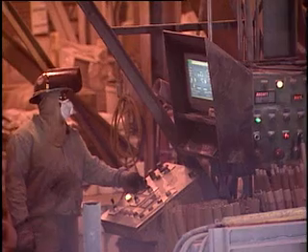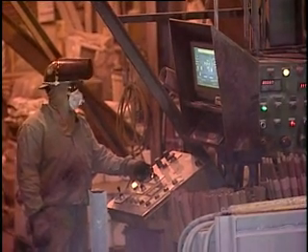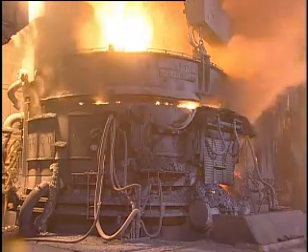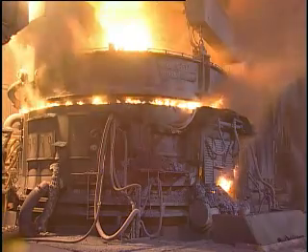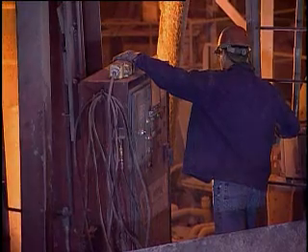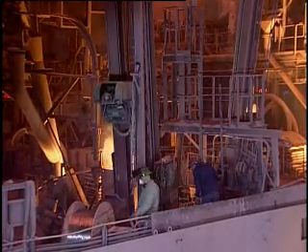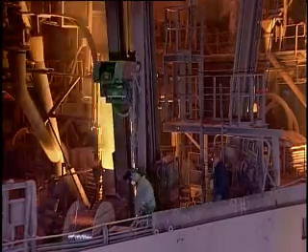One, it allowed us to alarm and shut down before we got holes, and that saved somewhere between 2 and 5% productivity just through elimination of downtime. It also allowed us to go to more advanced controls where rather than shutting the furnace off, we could just volt the furnace down. That gave us a 5 to 10% gain in average voltage, which is directly proportional to productivity.